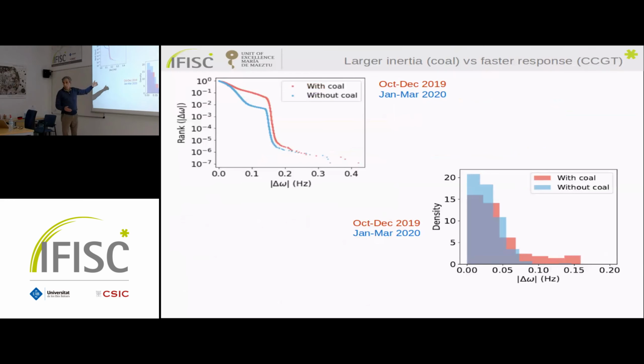So let's compare larger inertia, meaning when coal was there, with lower inertia but fast response—this is without coal, this is CCGT. As you can see, the fluctuations, and this is the probability density of fluctuations over the 3-month period, has been reduced a lot by incorporating fast response, despite the fact that we might have reduced the inertia.